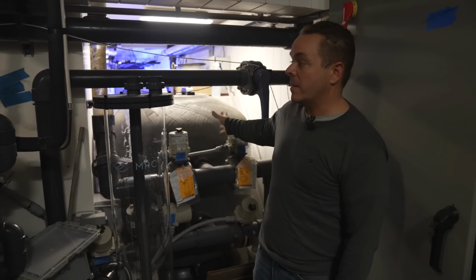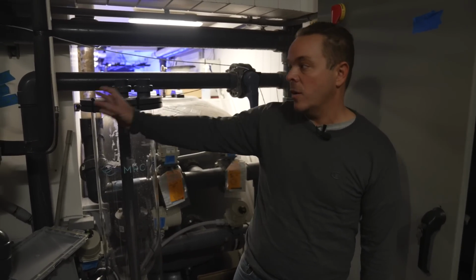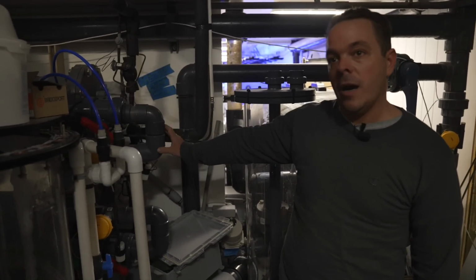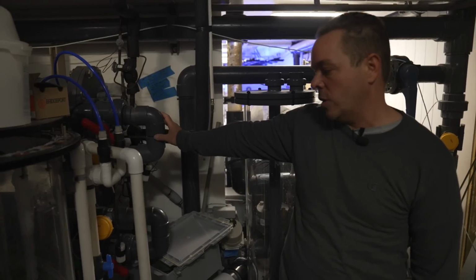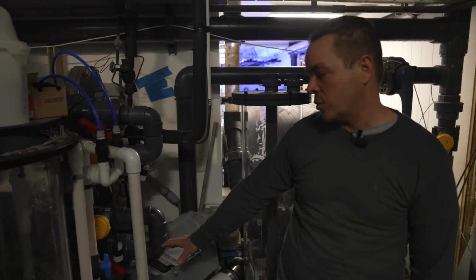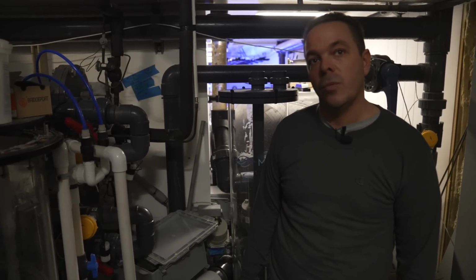The water exits the sand filter, and then it goes through 2 titanium heat exchangers, which are for the chiller, and a 3rd titanium heat exchanger on the bottom here that's connected to the boilers for heating. We split up the chilling and heating like this, part in the main system, part in the open system. So God forbid we had a system go down, the tank is still operational, whether it be on the closed loop or the open system.